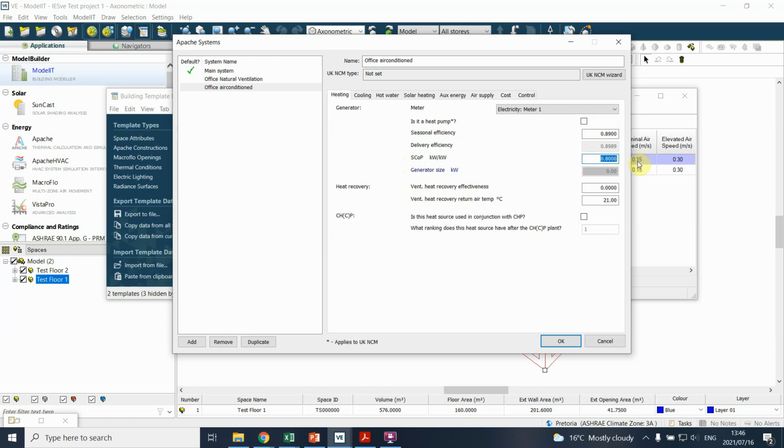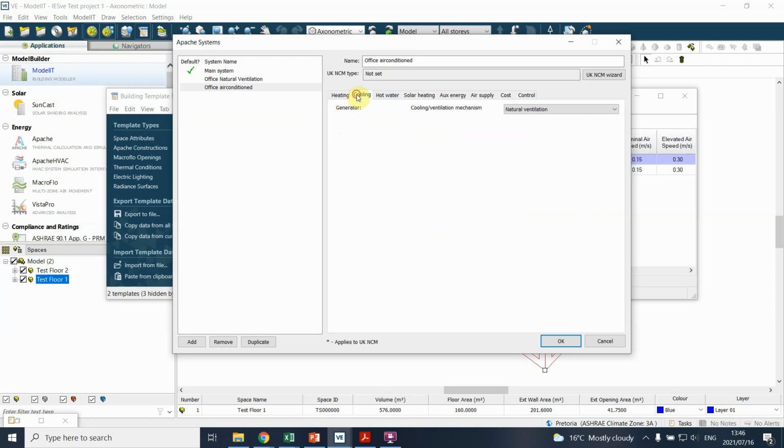And in South Africa, for heating, you can use it. The basic assumption would be a 3.4 for an air conditioning system. That's very basic. It's not necessarily adjusted. And the seasonal efficiency, I will just simply keep as it is. Again, this is based on studies by the Department of Energy, where they looked at what basic commercially available air conditioning systems are. If you're designing with a mechanical engineer, then just contact them and get the COP or this SCOP from them.